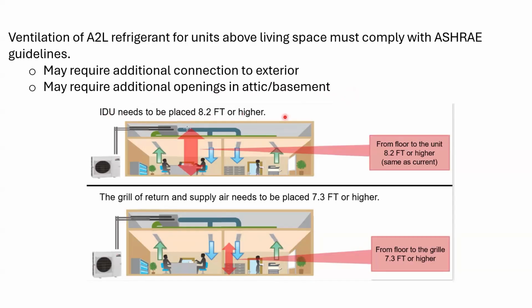We just looked at that in this scenario. So let's consider maybe a PEAD unit, 1-to-1 setup right here. From the floor to the unit, is it 8.2 feet or higher? Same as current. And then the grills on the return and supply side need to be placed 7.3 feet or higher. So meaning no floor registers or sidewall, etc. Again, return and supply need to be placed 7.3 feet or higher. So if we have a refrigerant leak, we're not pulling it back into the ducting, dispersing it throughout the home.